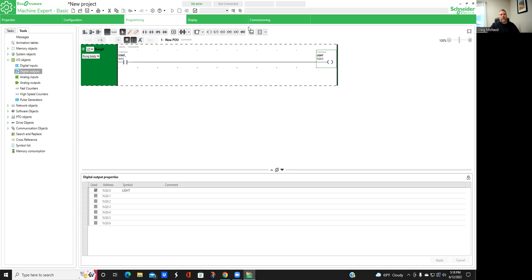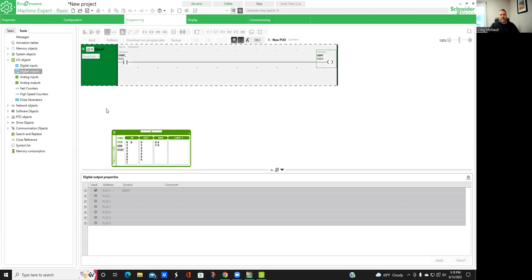Now we're going to go up here — watch my mouse — we're going to go to this little cross where it says Launch Simulator, and click that. We're going to test our project. As soon as this sets up, look at your box — you see how we have a checkmark in green. That's basically telling us we have a complete circuit. If we don't have a true circuit — if something is missing, whether it be the address or something else — we would know we have more stuff to do before trying the simulator. We want to check it with the simulator before we upload to the actual controller, to make sure everything is true and we're uploading a complete program.